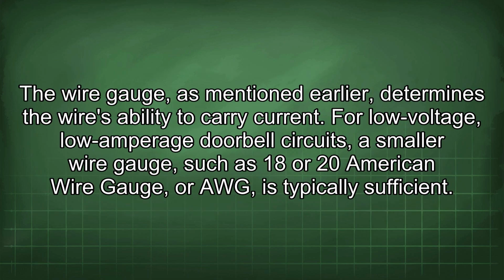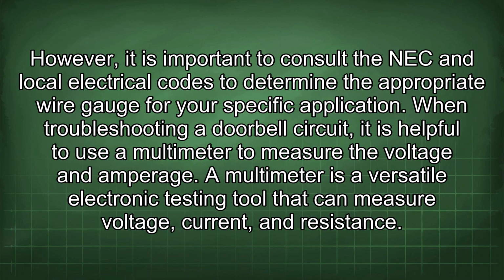The wire gauge, as mentioned earlier, determines the wire's ability to carry current. For low voltage, low amperage doorbell circuits, a smaller wire gauge, such as 18 or 20 American wire gauge, or AWG, is typically sufficient. However, it is important to consult the NEC and local electrical codes to determine the appropriate wire gauge for your specific application.